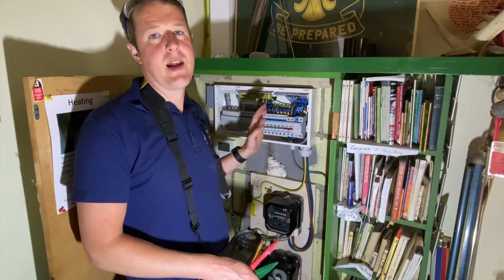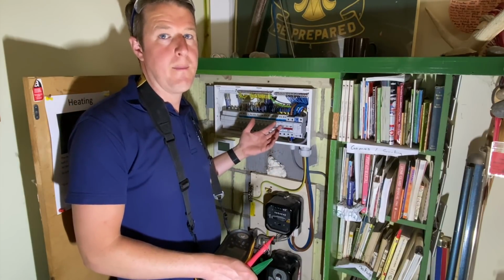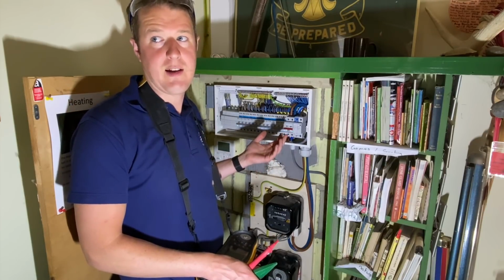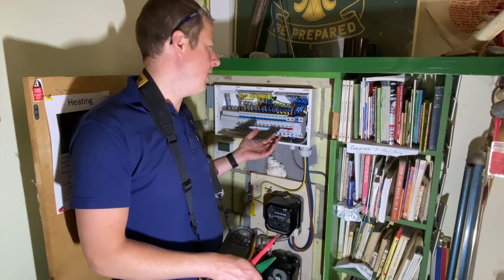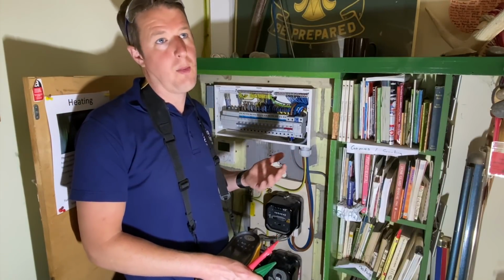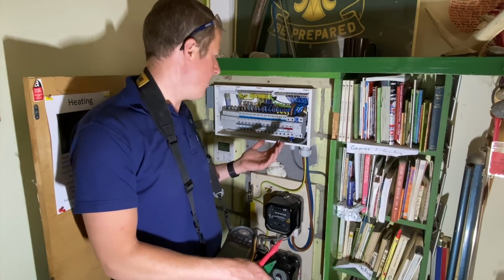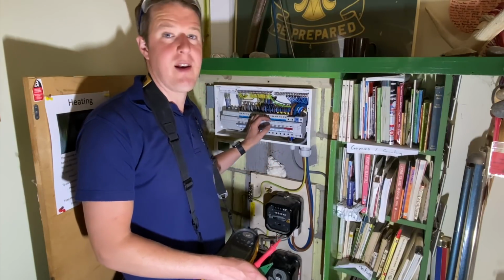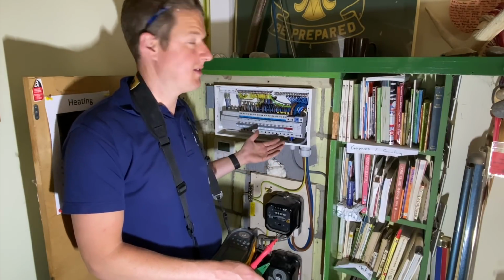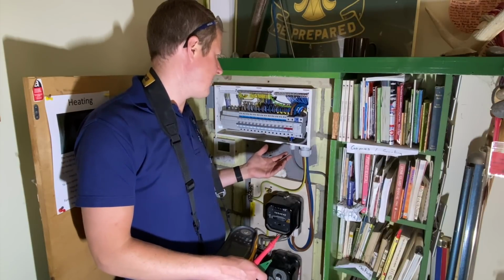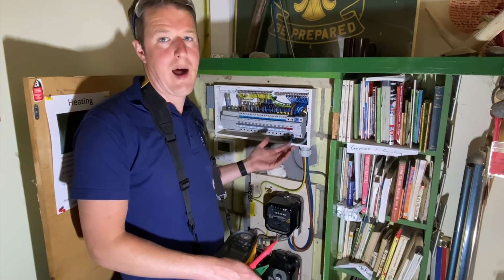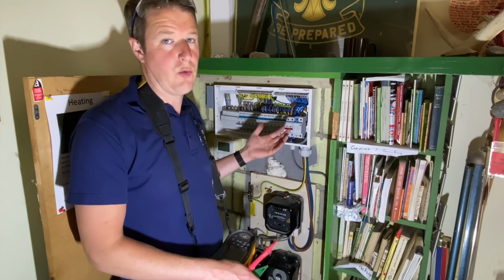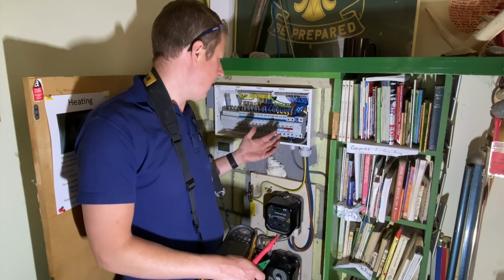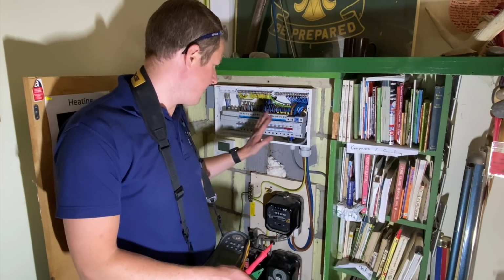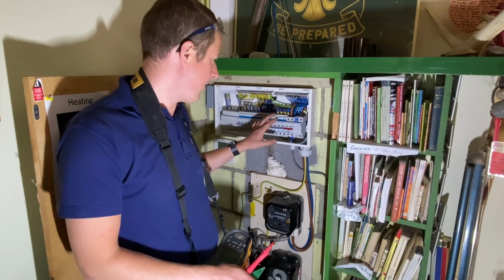Now we did carry out an EICR before, so that we knew the state of affairs before we got into changing the consumer unit. So although we have test readings for most of the circuits in the property, we have changed fundamentally the dynamics of the circuits when we've changed the consumer unit. So we do need to do those tests again just to make sure that everything's safe and all the readings are correct. So I'm going to start off, the board's dead at the moment apart from the main tails which are coming in.